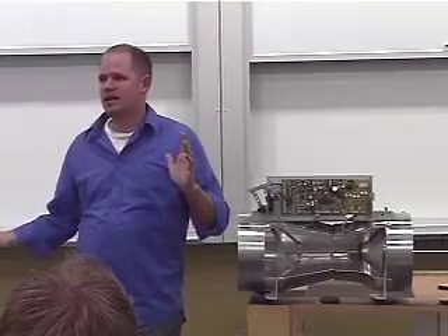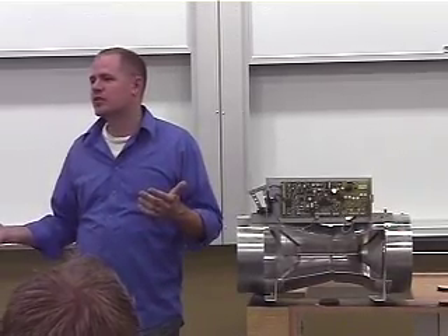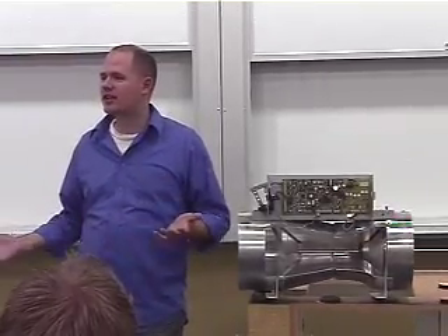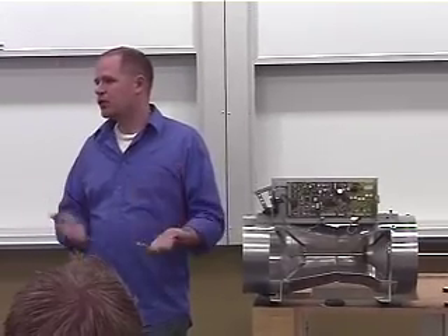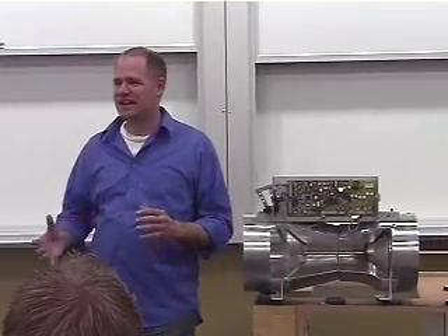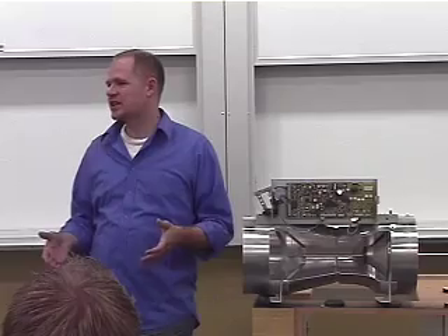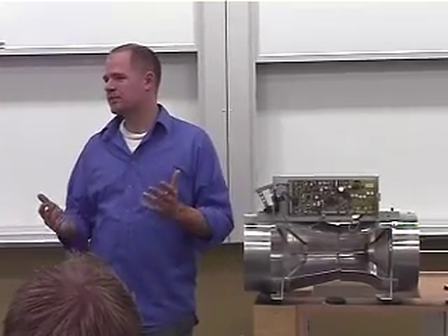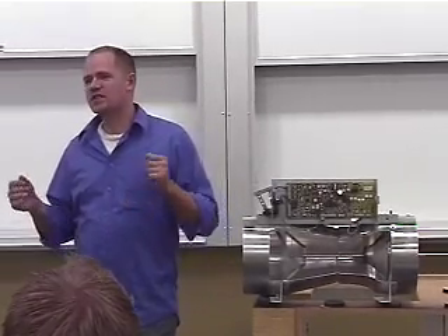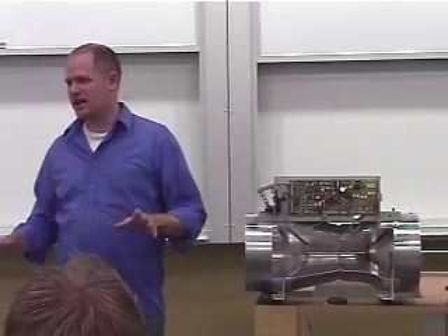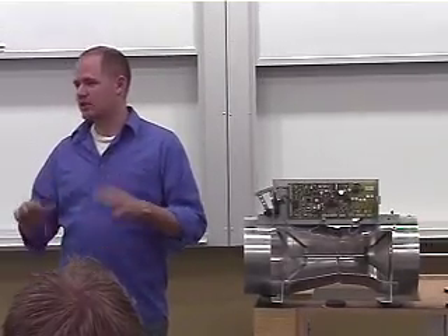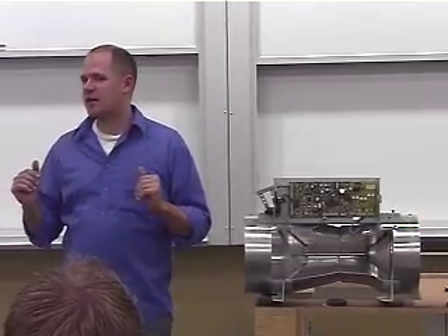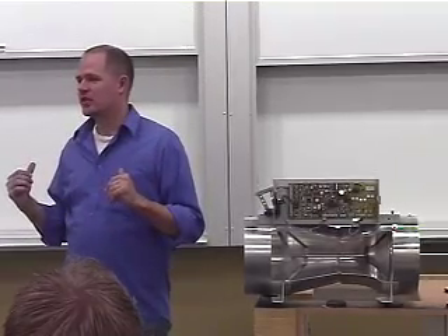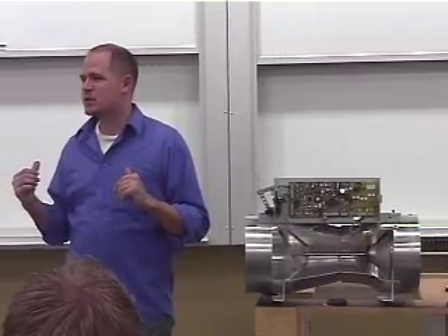Because it knows this was the temperature demand in the room, there's no reason to go wide open, we already know we have our offset, everything's good. Fume hoods are the things that kind of change the dynamics of what you're doing. When you have fume hoods in there, typically you want your fume hoods to fail open. That way, if somebody messes with the sash, it still has as much flow as it can get, so everything's happy. And then that would mean that your other flows need to fail in the correct positions as well.